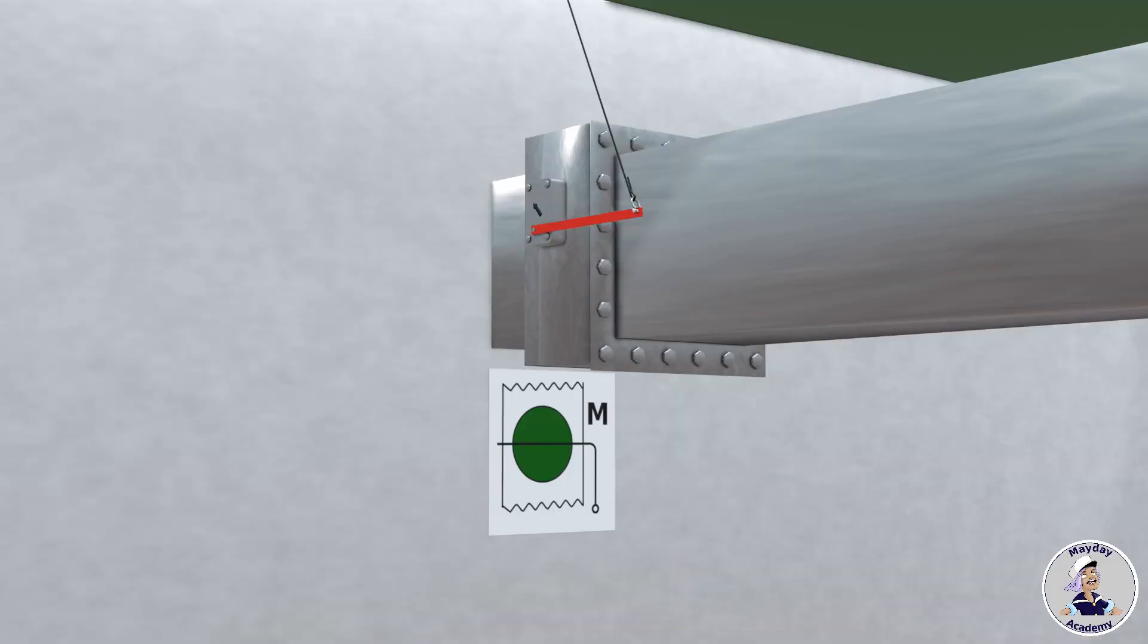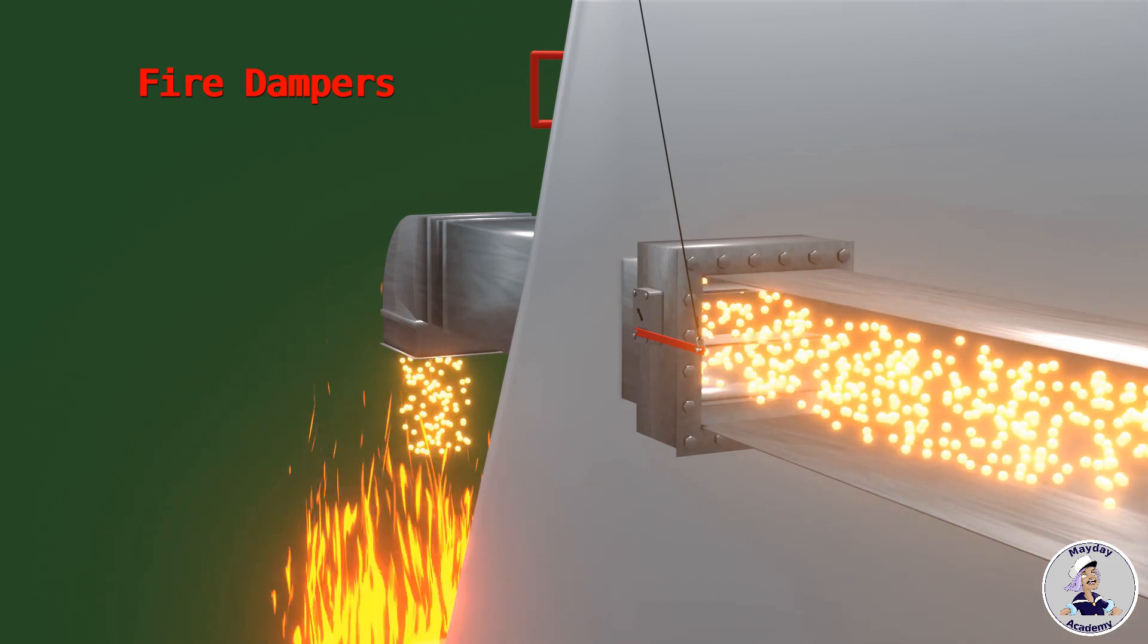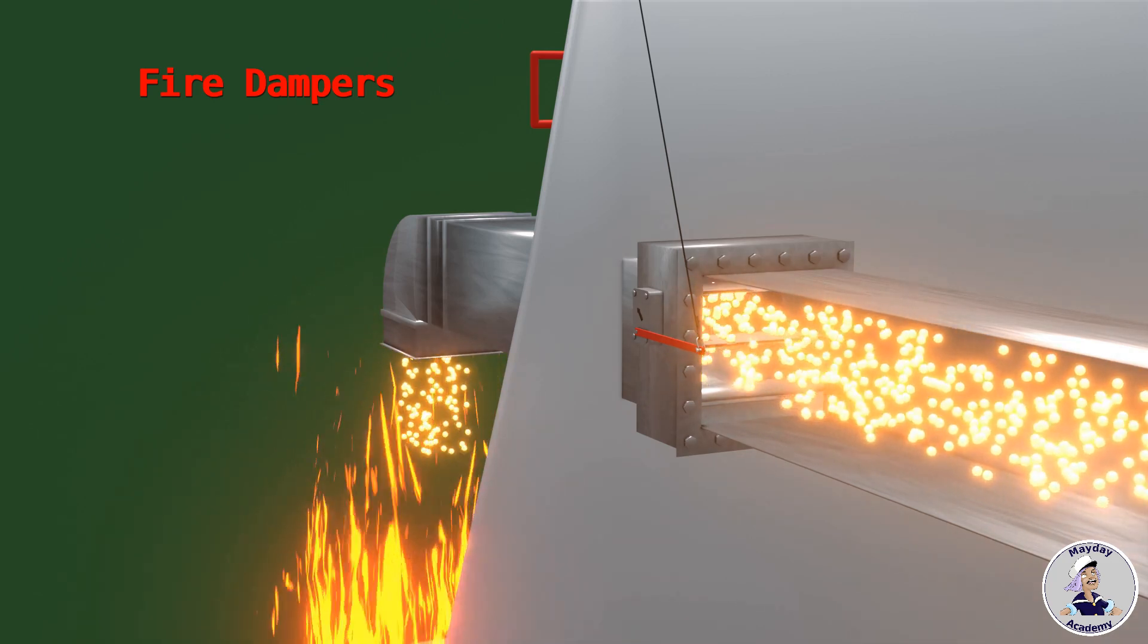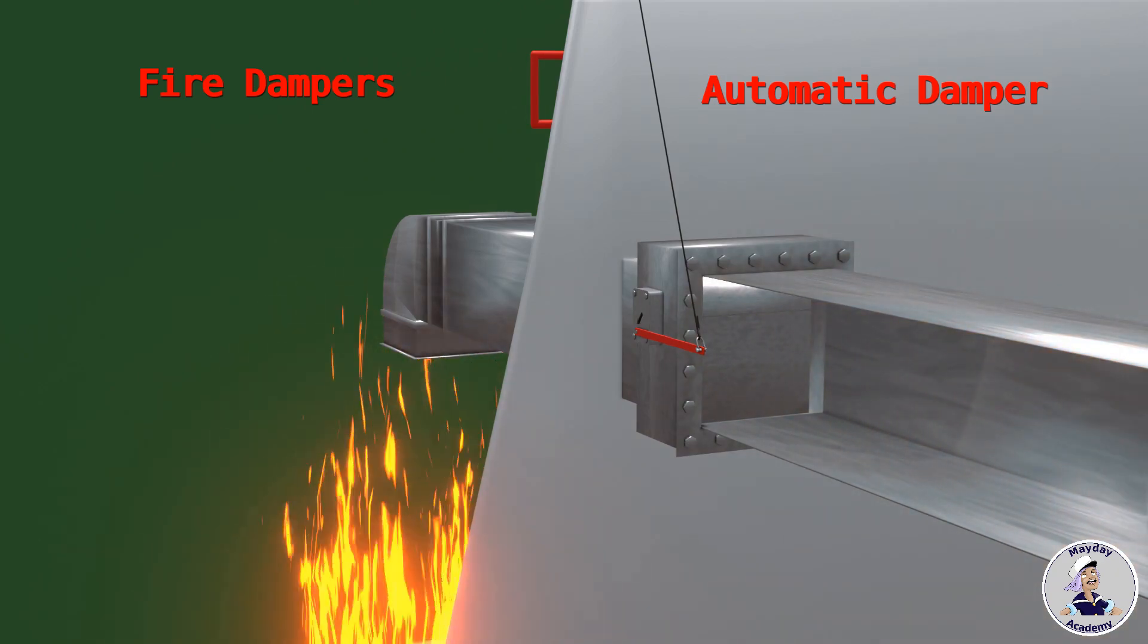Let's start with fire dampers. As per SOLAS regulations, dampers must be installed within all ventilation ducts penetrating any Class A compartment. When a fire occurs, the heat-sensitive element in the fire damper detects the rise in temperature and promptly closes the damper blades, effectively blocking the passage between compartments.